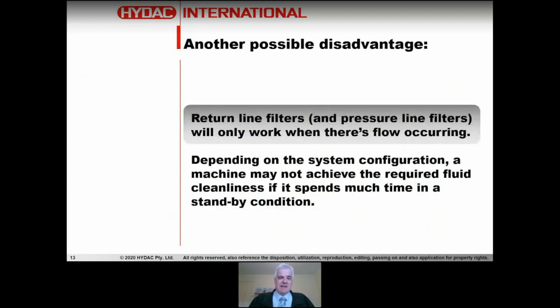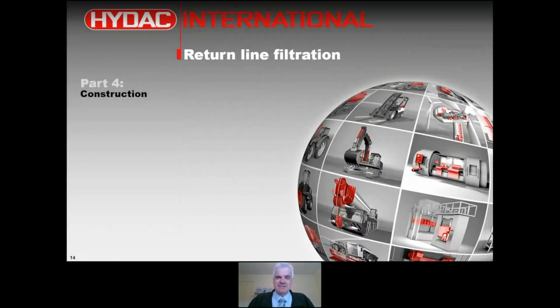Return line filters and pressure line filters will only work when there's flow occurring. This becomes an important part of system design because a machine may not achieve the required fluid cleanliness if it spends much time in a standby condition. For example, a system with a variable displacement pump will only give you flow when actuators are moving. Return line filtration is very common, but sometimes it needs to be supplemented because of these disadvantages.